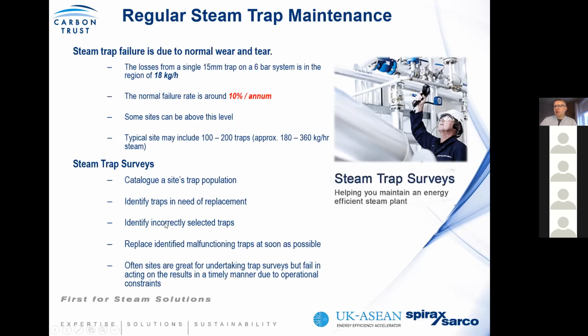Spirax Sarco, like any other trap manufacturer, will recommend a certain trap for a certain application. Although some traps are more expensive than others, each is designed for a specific purpose, so you need to install the trap that's designed to do what it's meant for. In other words, you should be looking not at initial cost, but at life cycle costs and reducing system maintenance costs. Unfortunately, what we're finding is that sites that undertake trap surveys are good at doing the survey, but acting on the findings can be an issue due to operational constraints. So we are trying to ease those procedures through what we call a double block and bleed type trap, where you can do the isolation and remove the failed trap quite effectively.